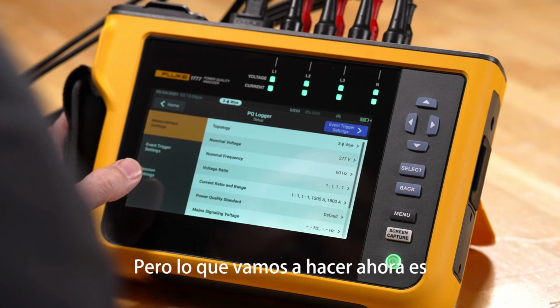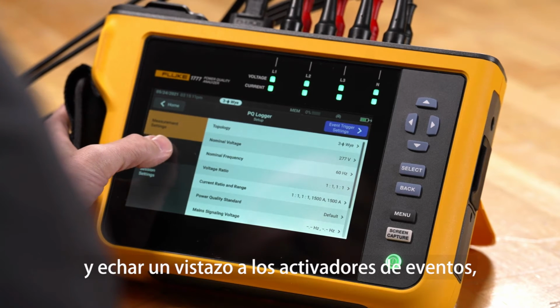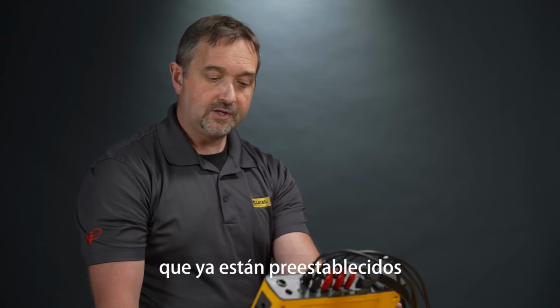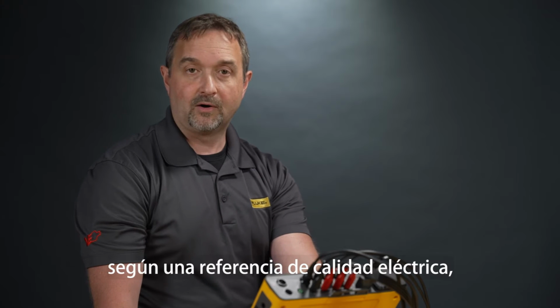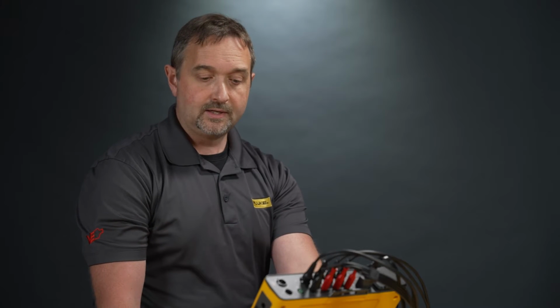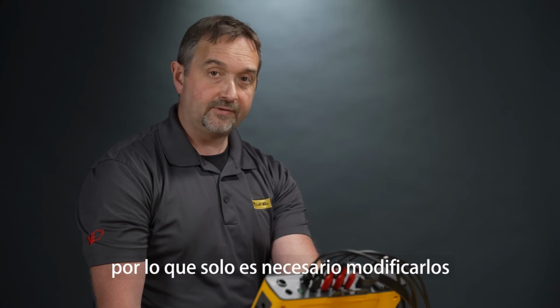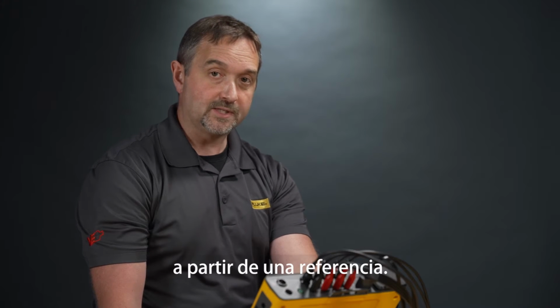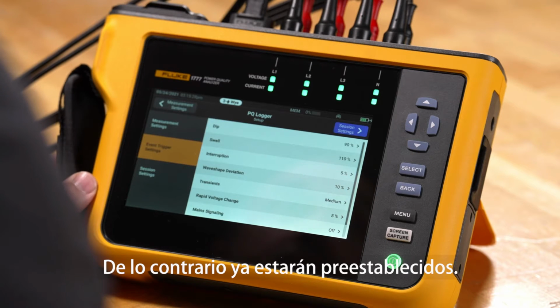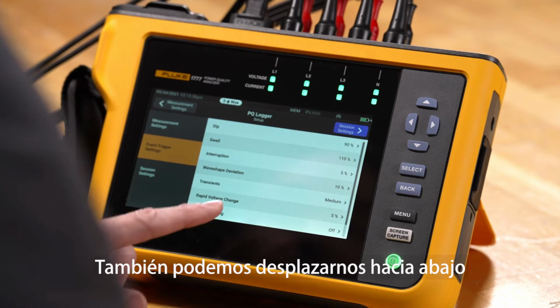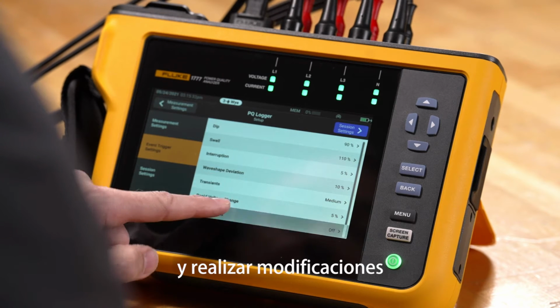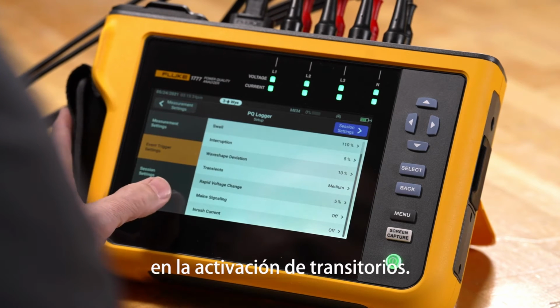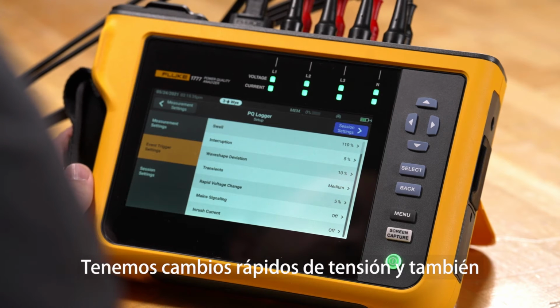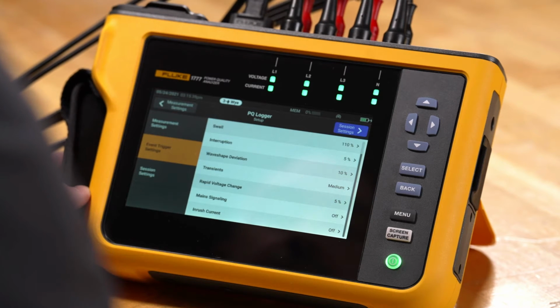But what we're going to do here is go down and take a look at our event triggers. And event triggers are already preset based on a power quality standard for you. So you don't actually need to modify these unless you want to make changes from a standard. We also have the ability to scroll down. We can make modifications to the transient triggering. We have rapid voltage changes, as well as inrush capture.